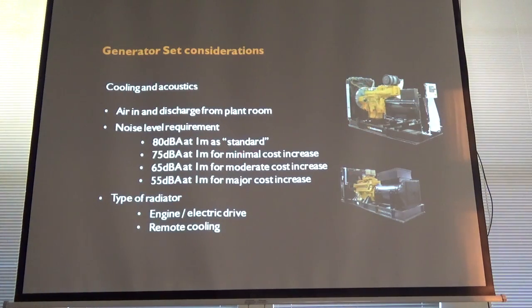So essentially you could be only saving 50% of the airflow that you normally require. And if you've got a remote cooled unit on the roof, multiple rads, attenuation issues possibly, 30 grade big attenuator on the top, electrical requirement for those radiators, you're going to have a cooling feed and return system. You'll need a simplex or duplex pump, depending on how concerned you are with resilience on that. You've got your plate heat exchanger there. You'll need an expansion system on that.